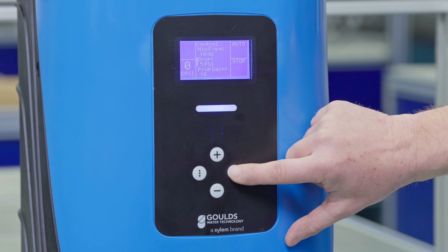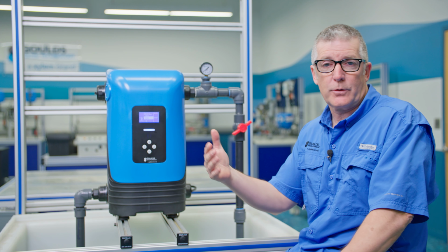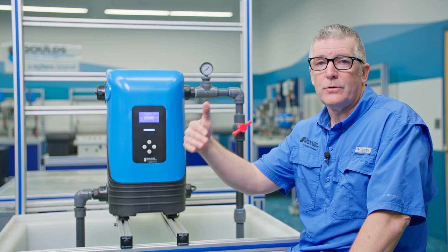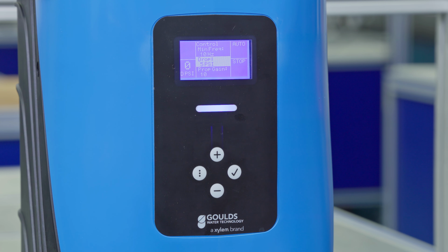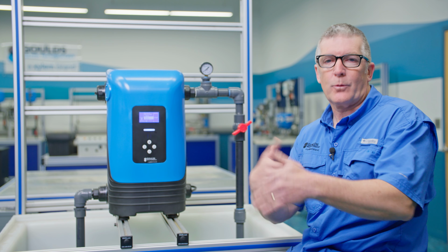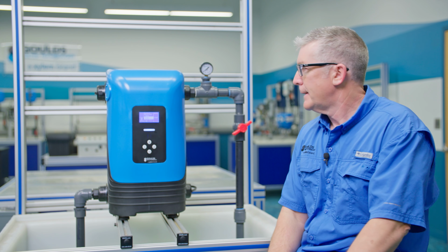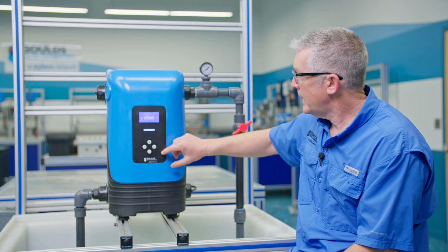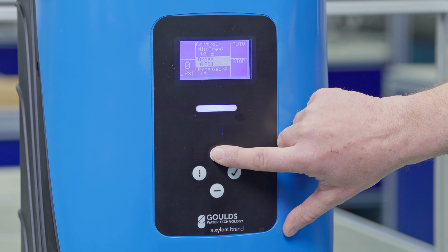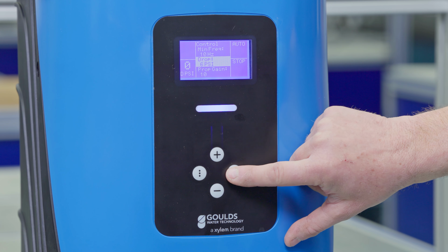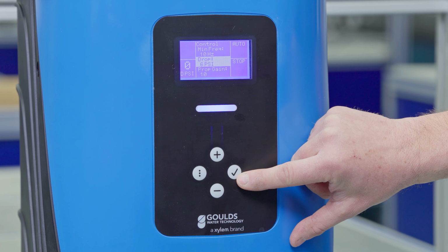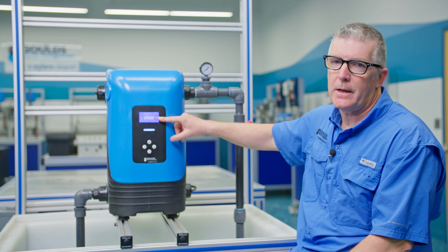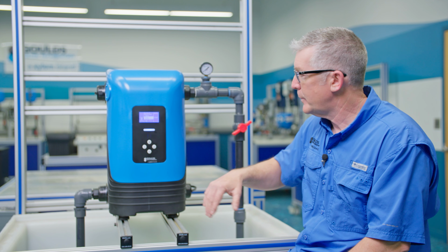Next is the drop. And drop is your restart, your pressure drop. In terms of PSI, what amount of PSI do you want that to fall to, right, after it's in sleep mode, before it restarts again? So that's your restart mode, and in this case here we call it drop. Typically it's 5 PSI, but again, you could change it, right? So you could play around with that and change it. Typically 5 PSI is pretty common for your restart value, and that is, in this case, 5 PSI below your set point, right? 5 PSI below your set point.